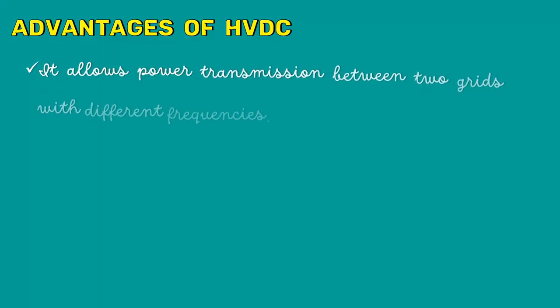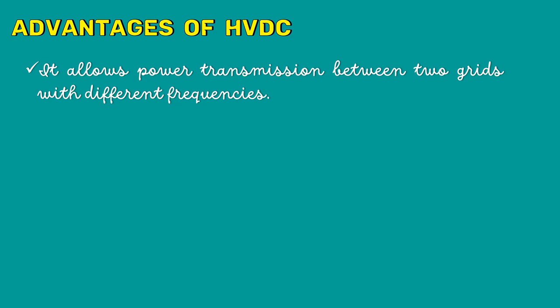If a country generates surplus electricity, they trade and share electricity with neighboring countries. The main thing to consider is that the two countries sharing electricity should have the same frequency. HVDC is very useful here because in DC, frequency is zero, so we don't have to worry about frequency matching. The first advantage of HVDC is that it allows power transmission between two grids with different frequencies.